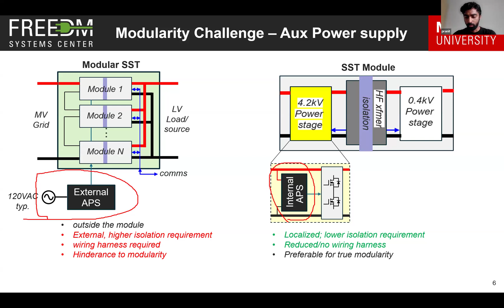Shown here is a switching cell diagram, a conceptual diagram, and therein sits the local supply that derives its voltage, its power, directly from the DC bus. One thing to note here is that the maximum bus voltage for a cell can go very high, reaching voltage levels of 2000 volts, and that brings up the first main challenge: high input voltage.